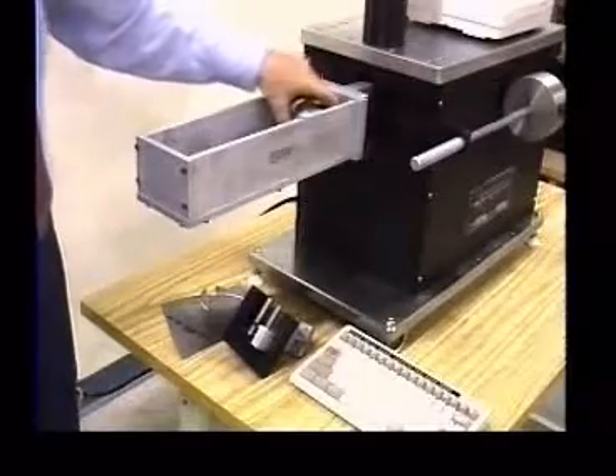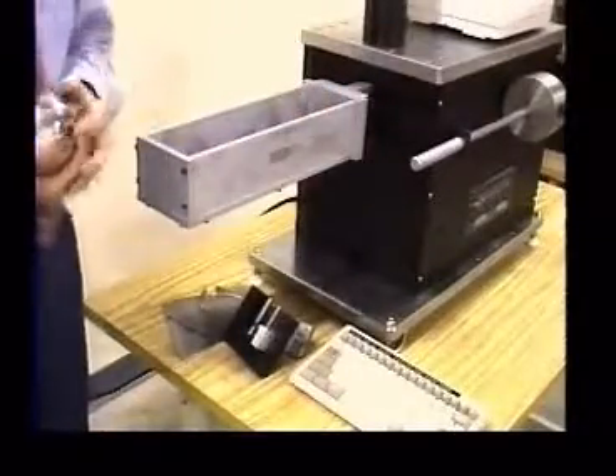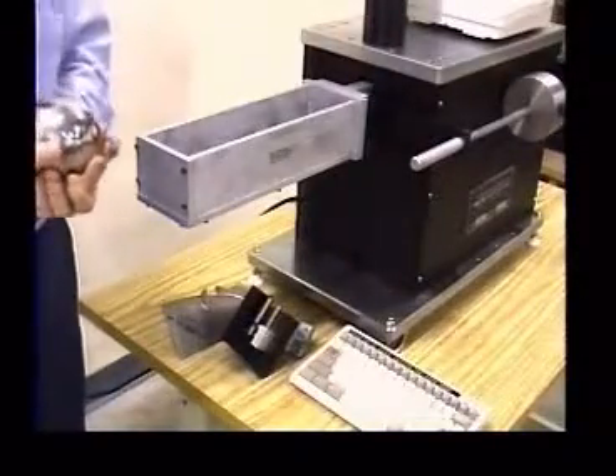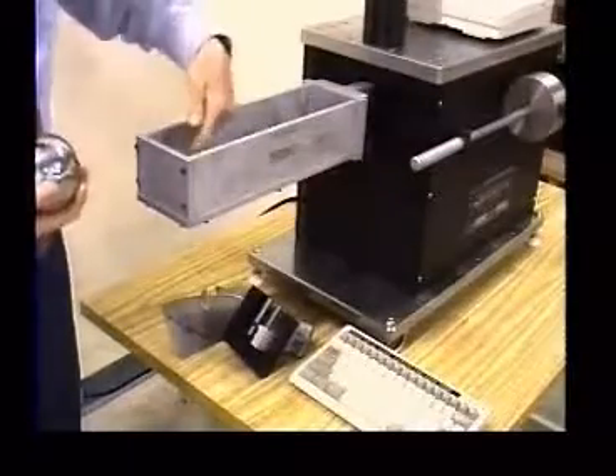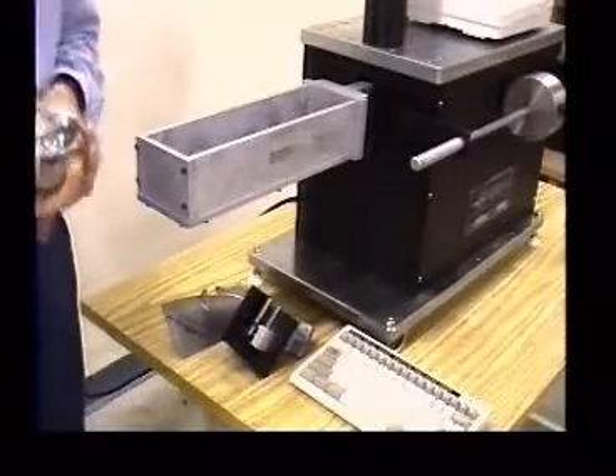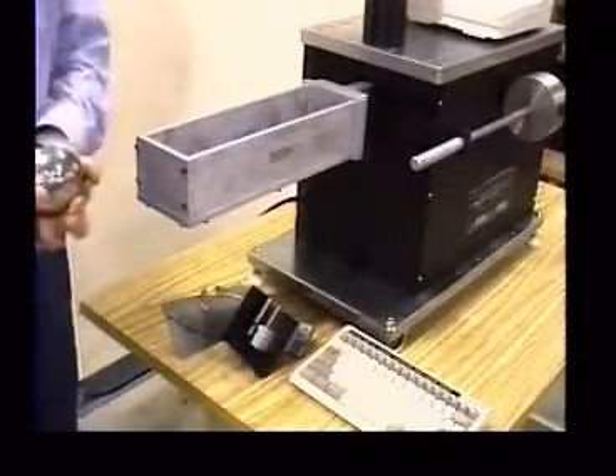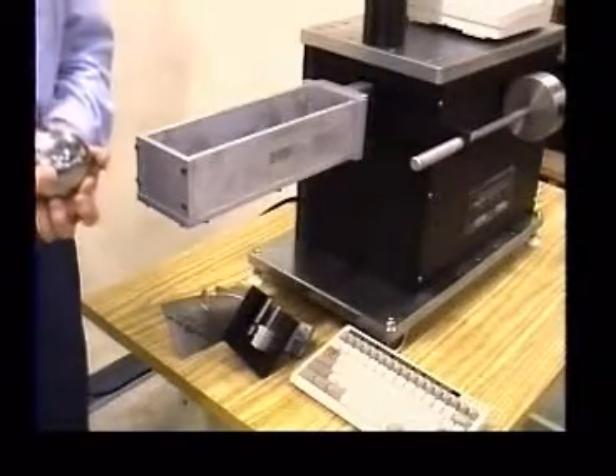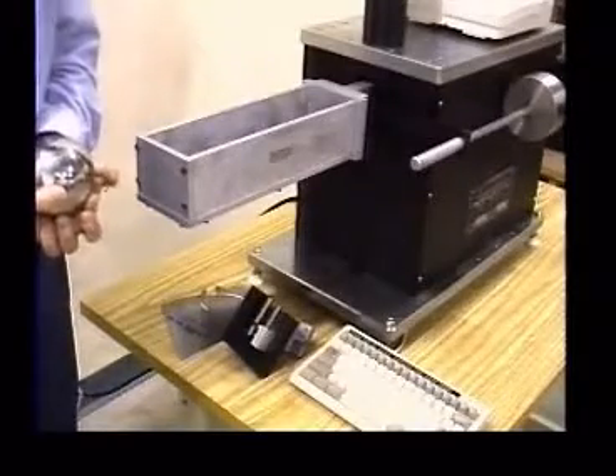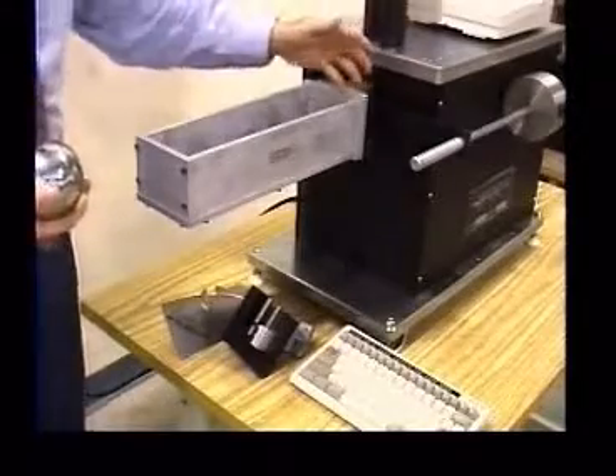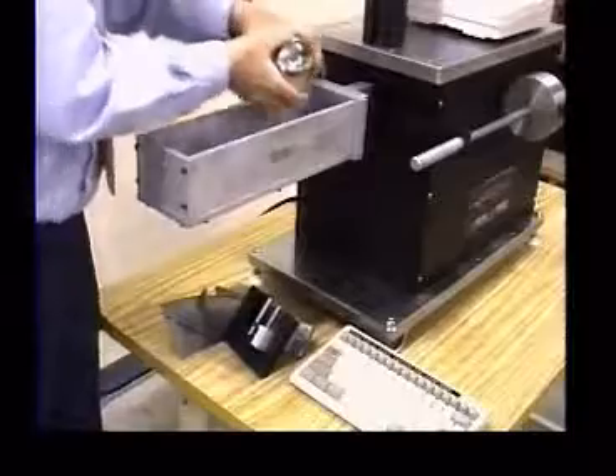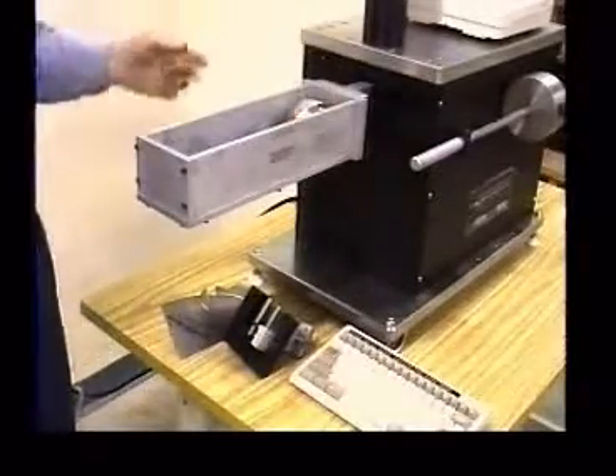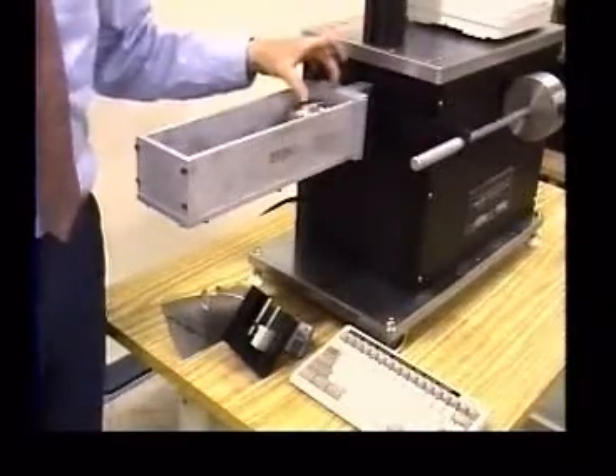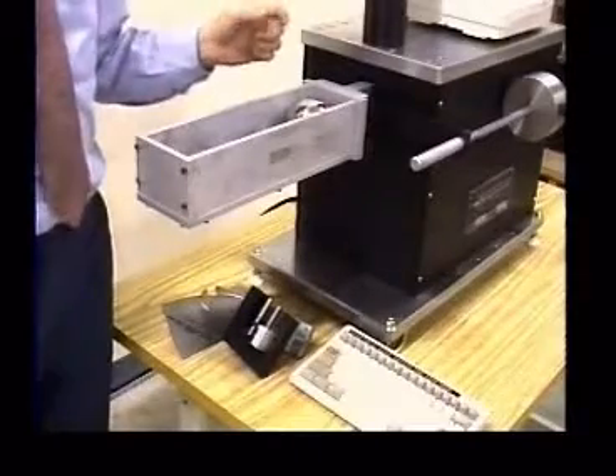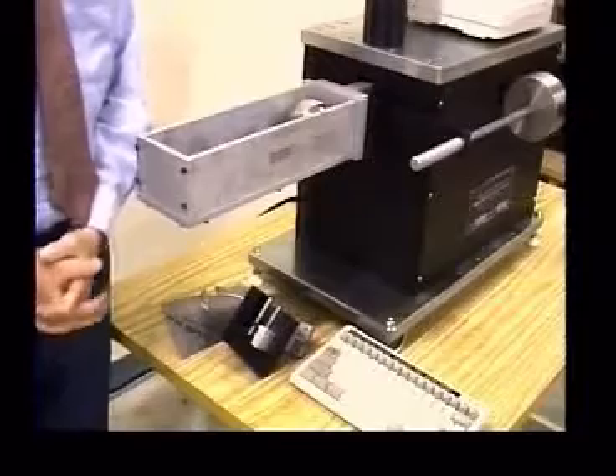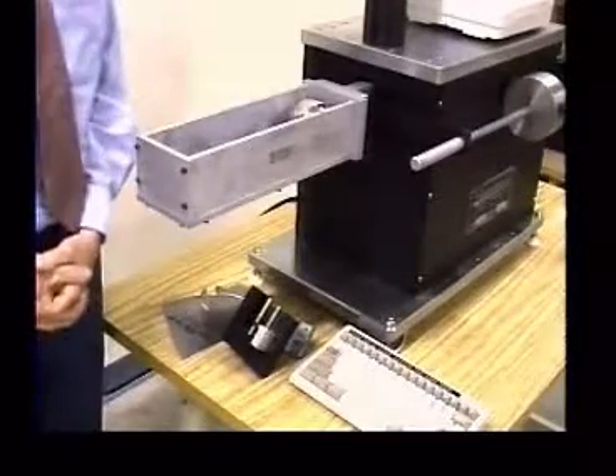The value of the calibration moment in the instrument is easily traceable to NIST because all we need to do is measure the weight of the ball, the diameter of the ball, and the distance between these 2 surfaces. We subtract the diameter of the ball from this distance and multiply it times the weight, and we have a number equal to the precise moment change for this calibration fixture. And then finally, if we want to determine the radius of the mounting plate on this machine, by placing the ball at this end of the machine, we have introduced a known mass at a known deflection from this mounting surface, and so mathematically we can determine the radius of the machine itself with an accuracy in the order of 100 millionths of an inch.